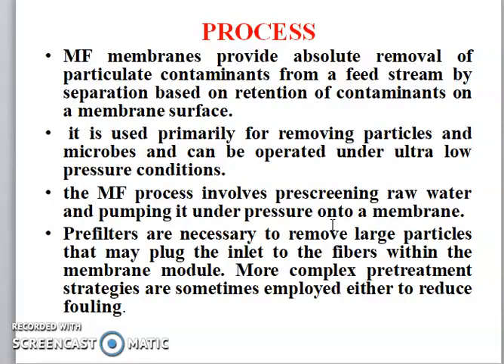The microfiltration membrane provides absolute removal of particulate contaminants from fluid streams by separation based on retention of contaminants on the membrane surface. It is used primarily for removing particles and microbes and can be operated under low-pressure conditions. The microfiltration process involves pre-screening raw water and pumping it under pressure onto the membrane. Pre-filtration filters are necessary to remove large particles that may plug the inlet to the fibers within the membrane module. More complex pre-treatment strategies are sometimes employed to reduce fouling.